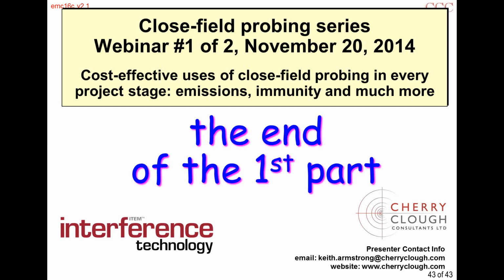In order to cross national boundaries, in order to be sold in the European Union, all you have to have is the CE marking on the product and the declaration of conformity. You don't have to make your technical documentation file available to anybody. So nobody can tell just from the declaration of conformity on what basis you decided that your product passed the tests. So yes, I've elaborated on that quite a bit because a lot of people, especially in America, seem to think that in order to put your CE mark on, you have to do the EMC tests and you have to pass them, but it's not true.